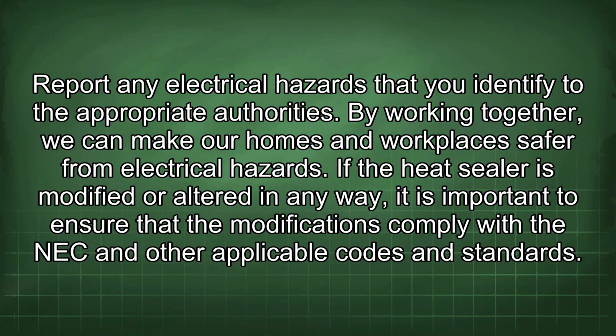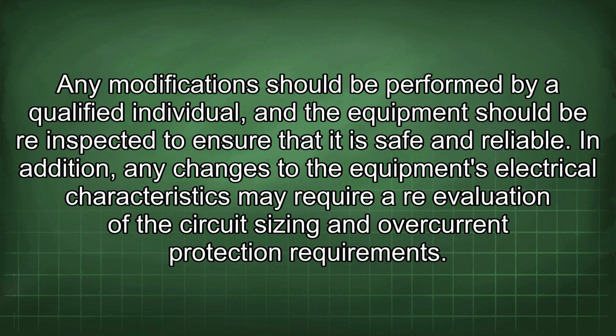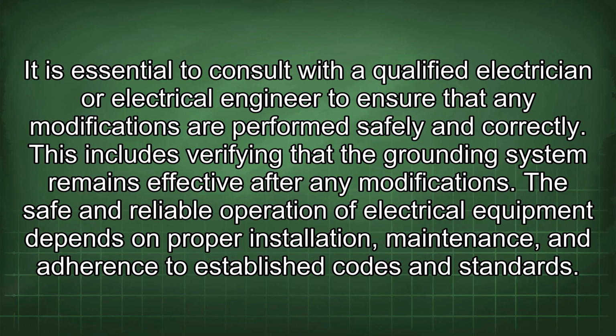If the heat sealer is modified or altered in any way, it is important to ensure that the modifications comply with the NEC and other applicable codes and standards. Any modification should be performed by a qualified individual, and the equipment should be re-inspected to ensure that it is safe and reliable. In addition, any changes to the equipment's electrical characteristics may require a re-evaluation of the circuit sizing and overcurrent protection requirements. It is essential to consult with a qualified electrician or electrical engineer to ensure that any modifications are performed safely and correctly. This includes verifying that the grounding system remains effective after any modifications.